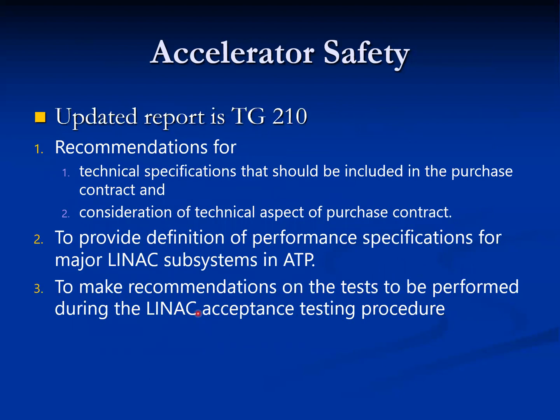The latest report is TG-210, which includes recommendations for technical specifications that should be included in purchase and contract considerations. It provides definitions and performance specifications for major linac subsystems in acceptance testing, and makes recommendations on tests to be performed during the linac acceptance test procedure to ensure the accelerator is safe to use.